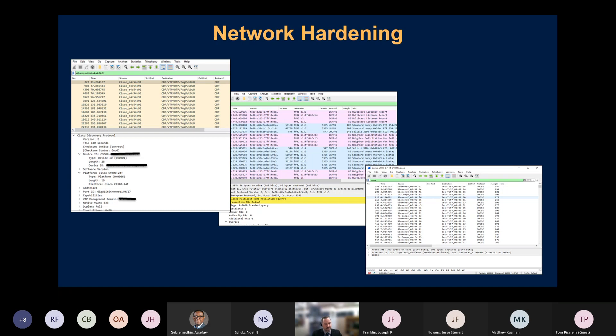LLMNR has many well-documented vulnerabilities and exploits. You can also reference STIG or SRGs for guidance on recommended configurations for most network devices. The last Wireshark capture shows a misconfiguration of the protection network using IEC 61850 — also known as GOOSE — not implemented per the standard. All the GOOSE traffic, which is a layer two multicast protocol, is all on the default VLAN, meaning it can just go everywhere. This causes a lot of unneeded network congestion and no prioritization of those time-critical protection messages.